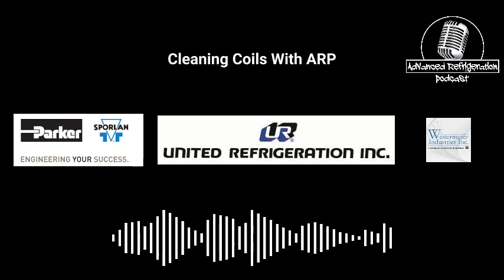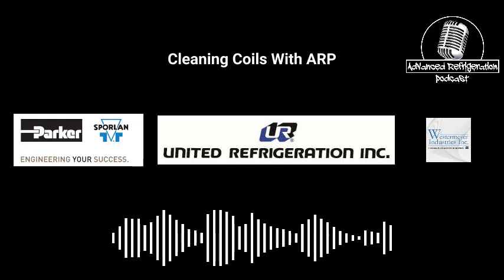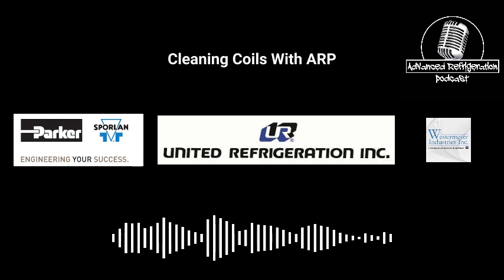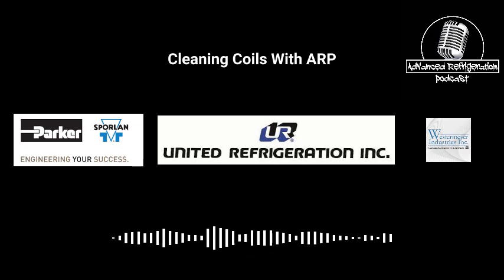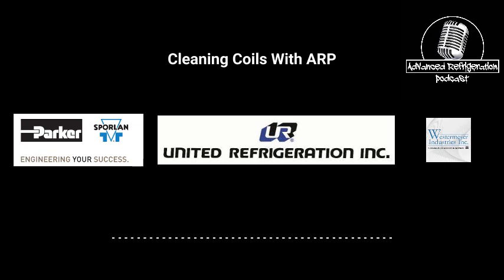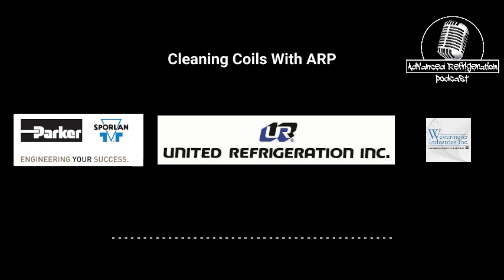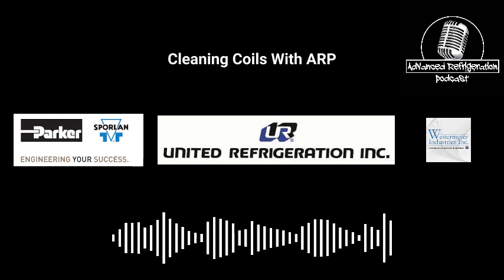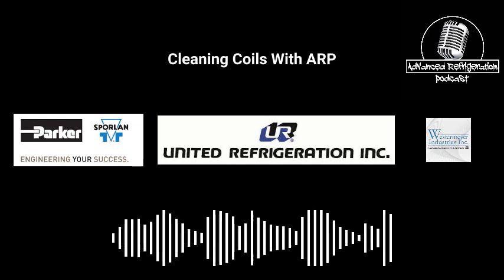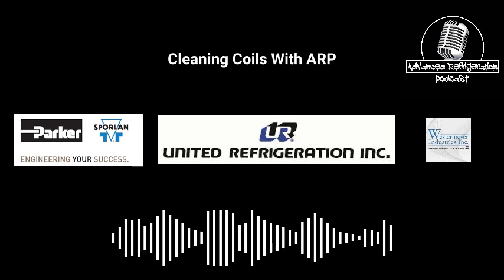You'll go to blow out a case, say the whole lineup's plugged up. We have this problem at multiple stores where the main lineup plugs. You can't get to the drain underneath the case. It's in a real bad spot. So you need to go from the farthest case and block the other two drains and blow it out that way. But generally, when you start plugging up like that, I guarantee the coils and the cases probably need cleaned. So that's one thing to keep in mind.